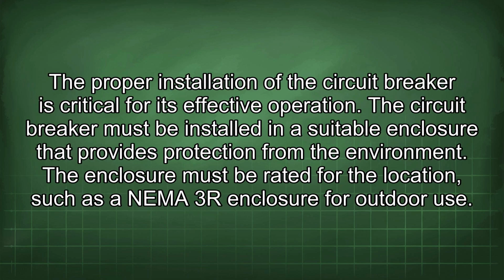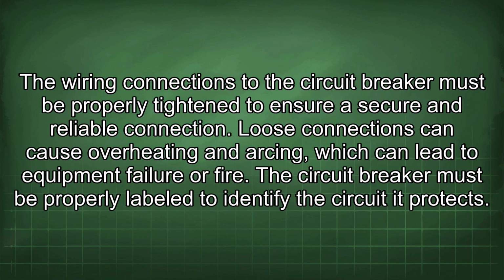The proper installation of the circuit breaker is critical for its effective operation. The circuit breaker must be installed in a suitable enclosure that provides protection from the environment. The enclosure must be rated for the location, such as an NEMA 3R enclosure for outdoor use. The wiring connections to the circuit breaker must be properly tightened to ensure a secure and reliable connection. Loose connections can cause overheating and arcing, which can lead to equipment failure or fire.